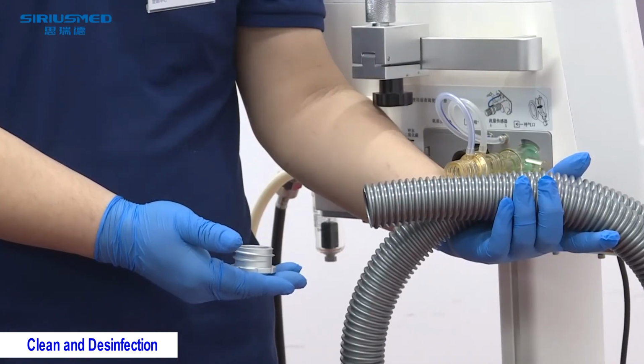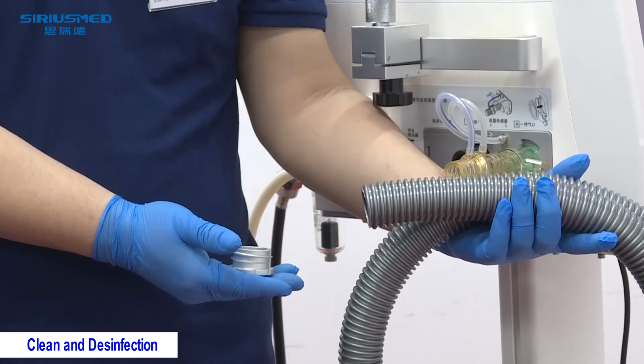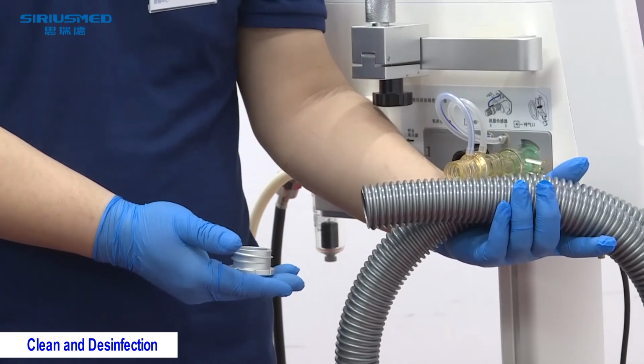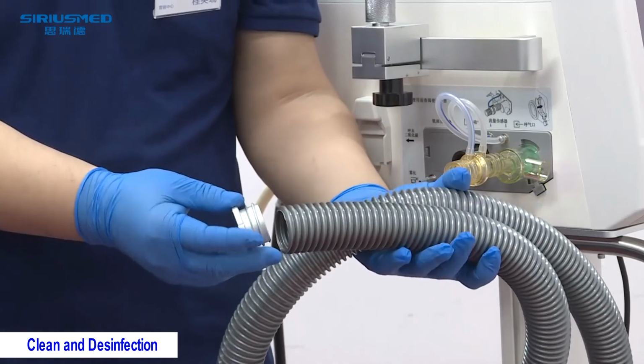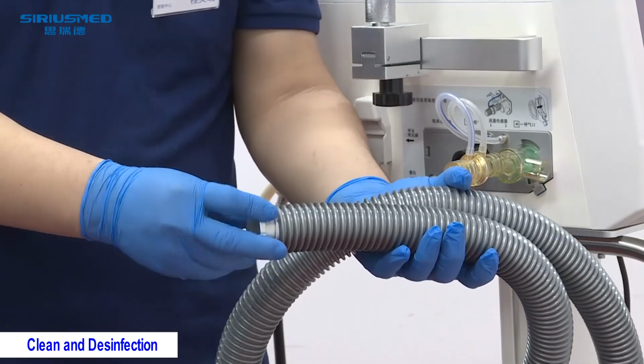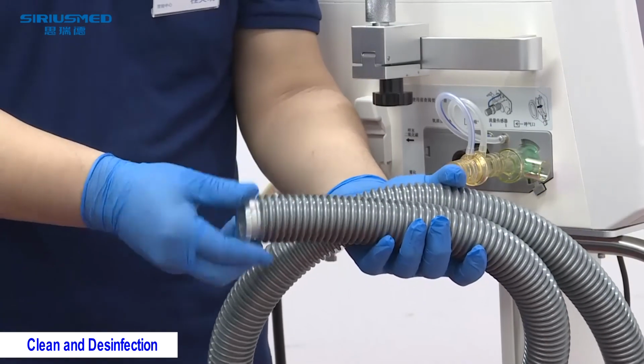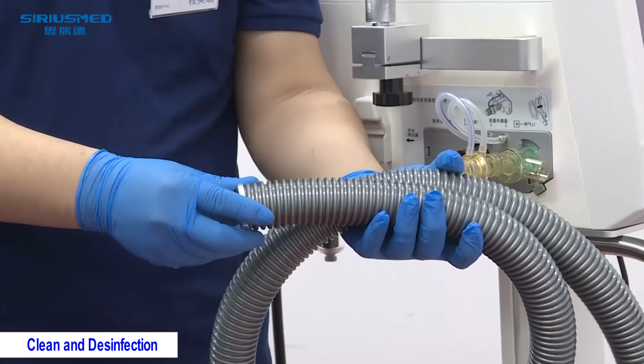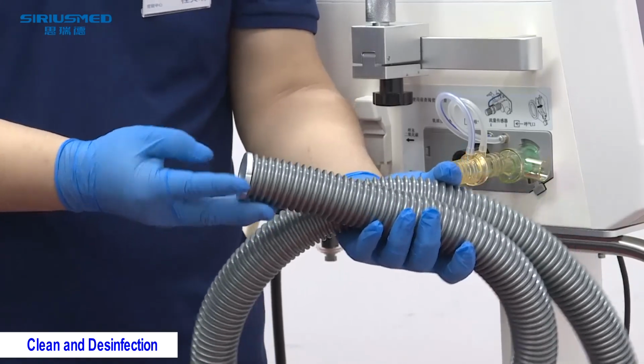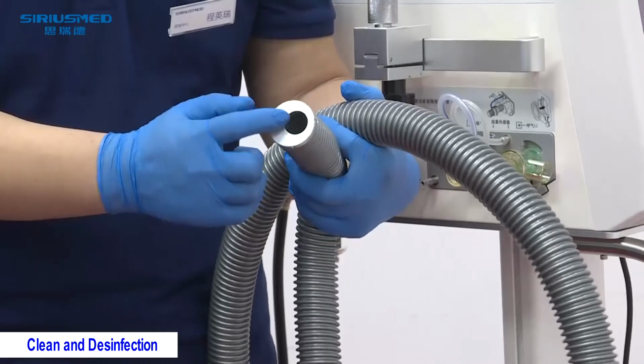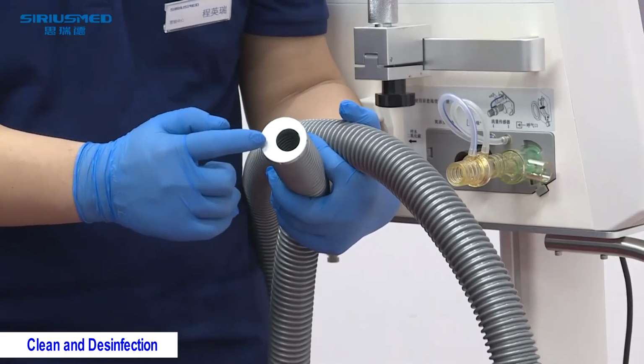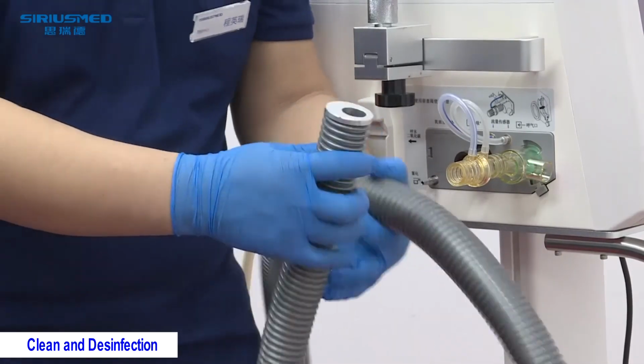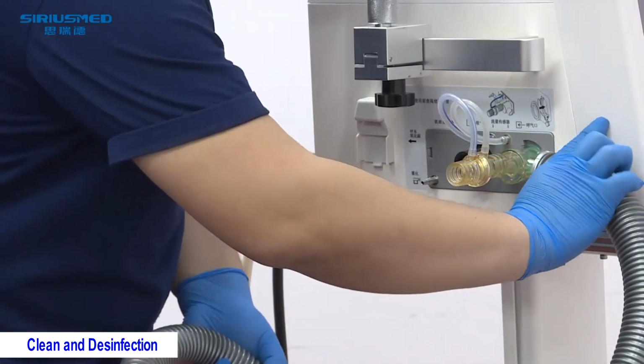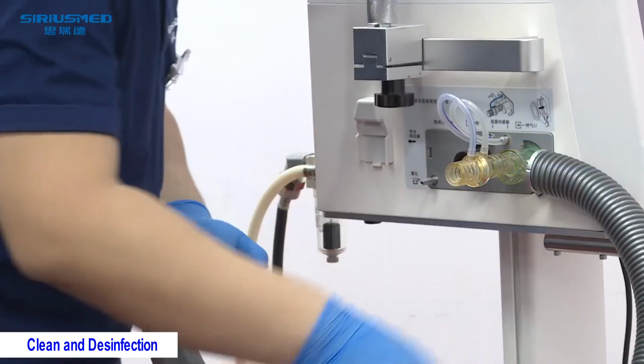After the disinfection, we need to pay attention to the connection of the metal connector to this exhaust hose. Please make sure you are turning it anti-clockwise to install. And see here the narrow side and the wider side. Keep the narrow side near the main unit and connect to the exhaust port.